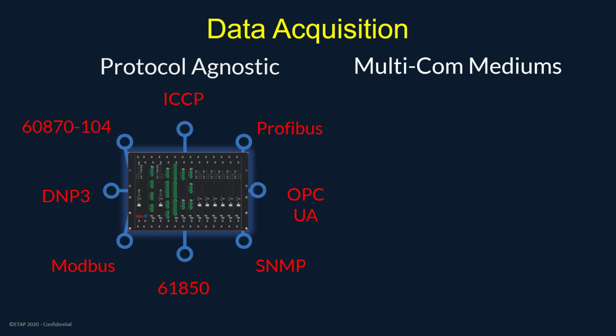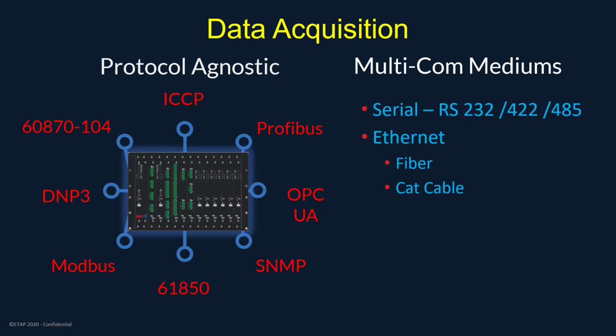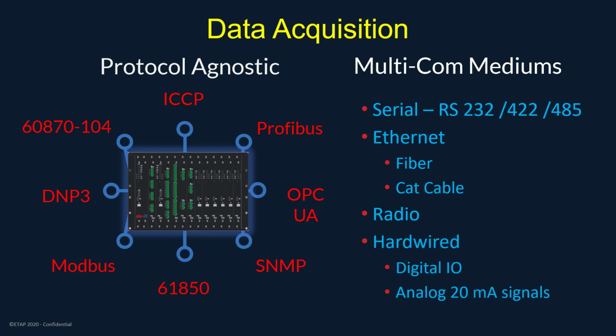The communication protocols include IEC 60870-104, DNP3, Modbus, IEC 61850, SNMP, Profibus, and directly from the processing server, it also includes OPC UA and ICCP for remote communications. The mediums of communication include serial RS-232, 422, and 485, Ethernet via fiber or CAT cable, radio communications, hardwired direct digital I/O and analog signals in 20 milliamps.